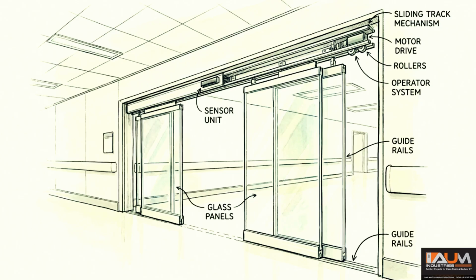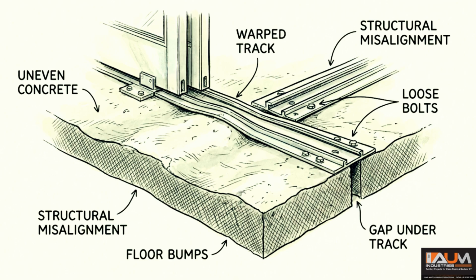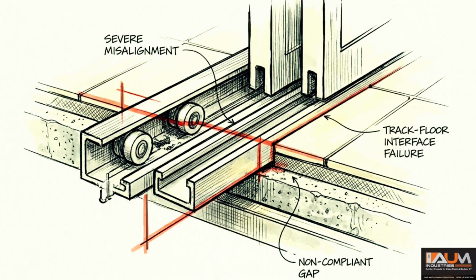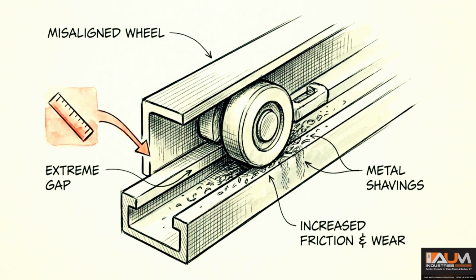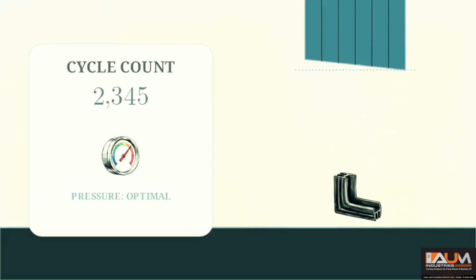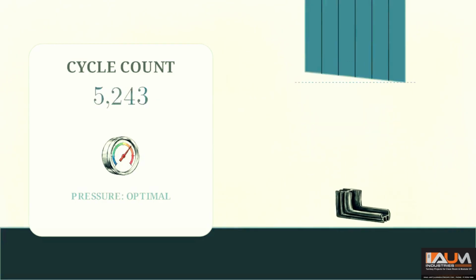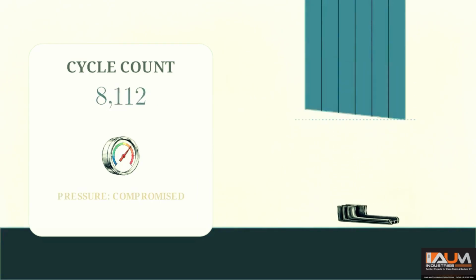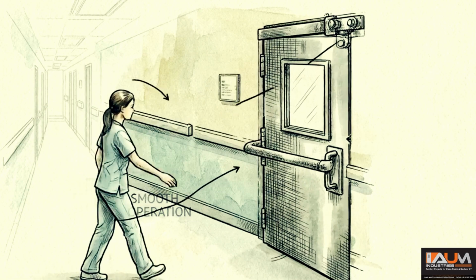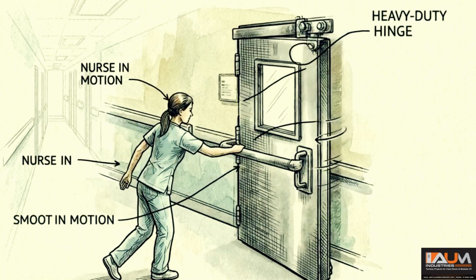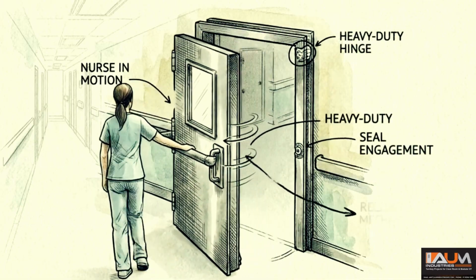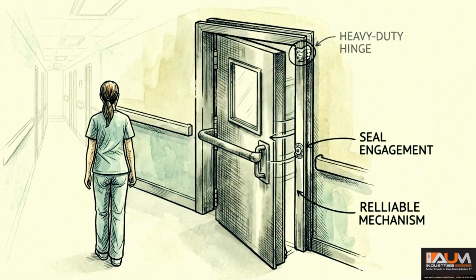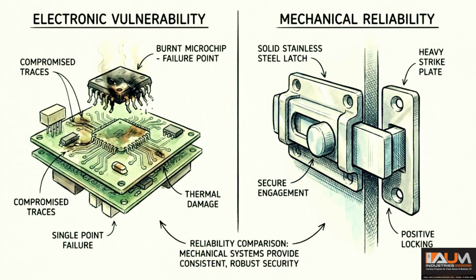There is a widespread assumption that every modern hospital should be outfitted with futuristic automatic sliding doors, but automation has strict physical vulnerabilities. If the structural concrete is poured with even a slight unevenness, or if the site coordination between the flooring and the door track is off by a few millimeters, the sliding track degrades. Over thousands of high-speed opening and closing cycles, that tiny structural misalignment grinds against the automation system, causing the hermetic seals to warp and fail. In high-traffic intensive care units, high-quality manual hermetic swing doors often provide more consistent reliability over long operational periods than complex automated systems. When you are engineering for life and death situations, consistent operational reliability has to take precedence over complex technology.